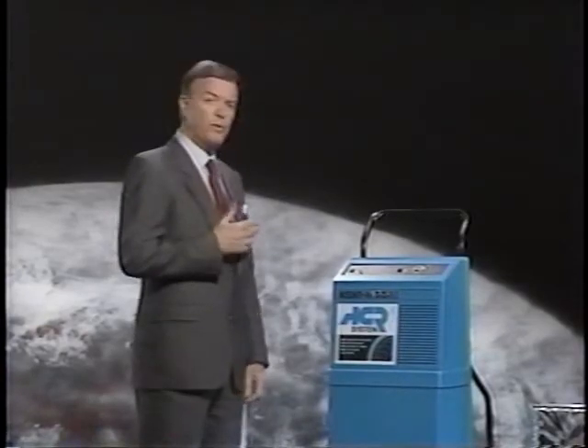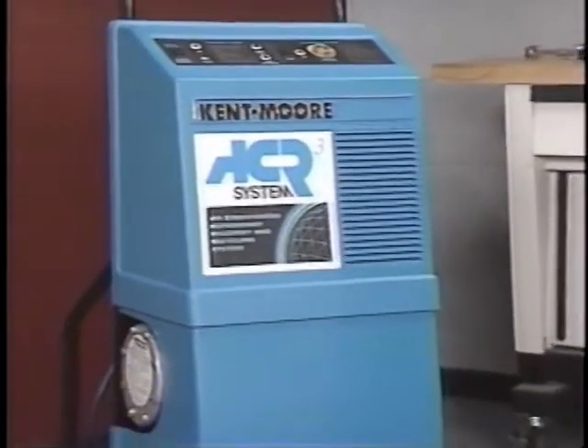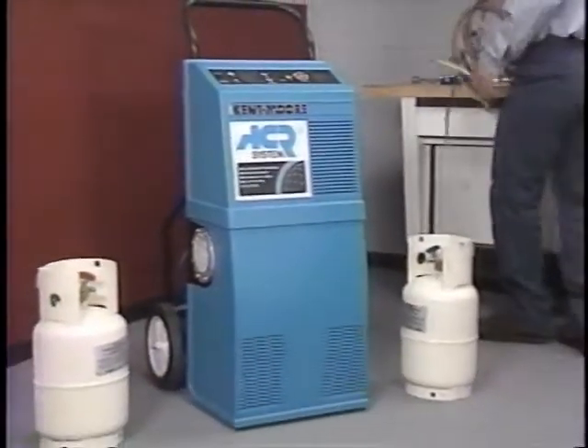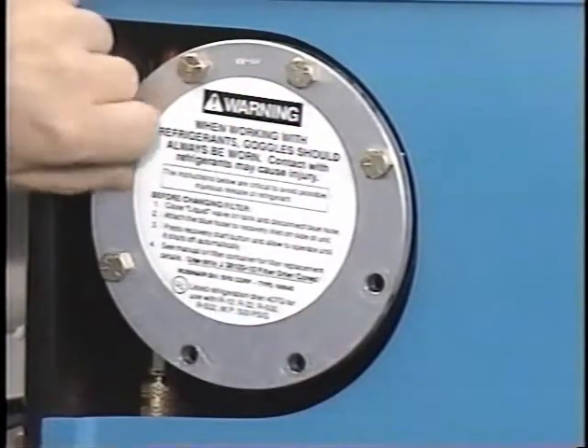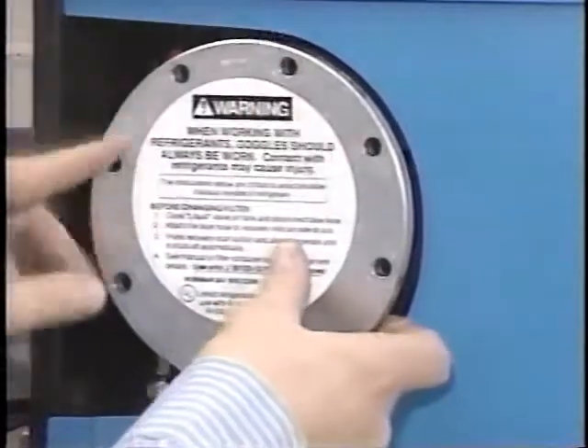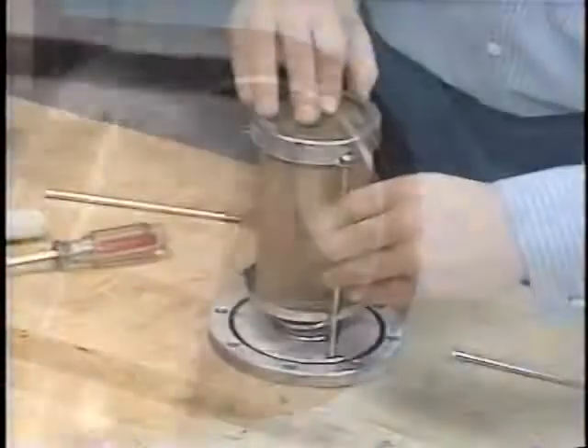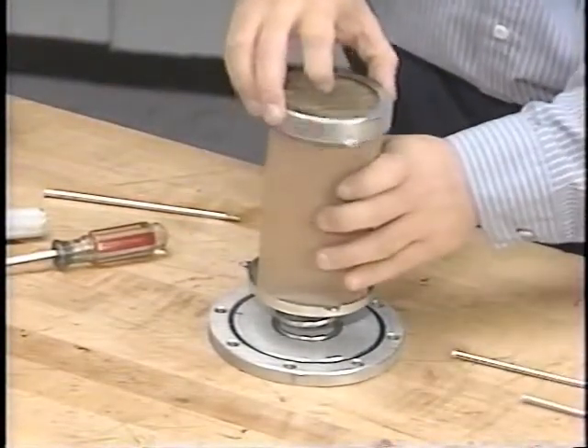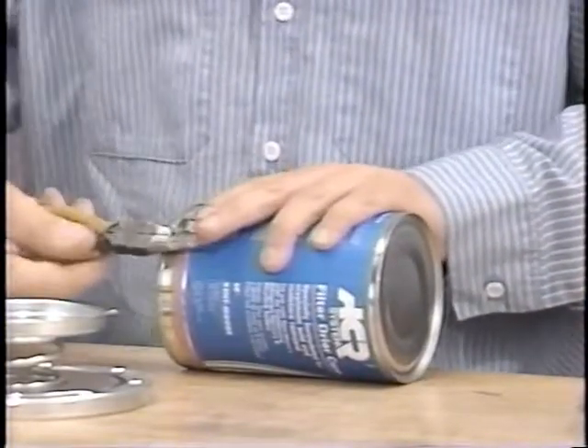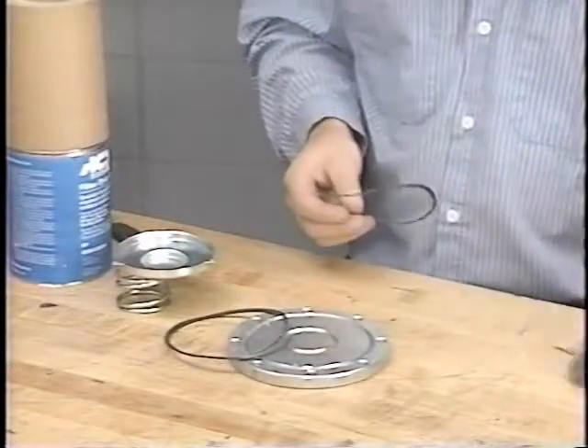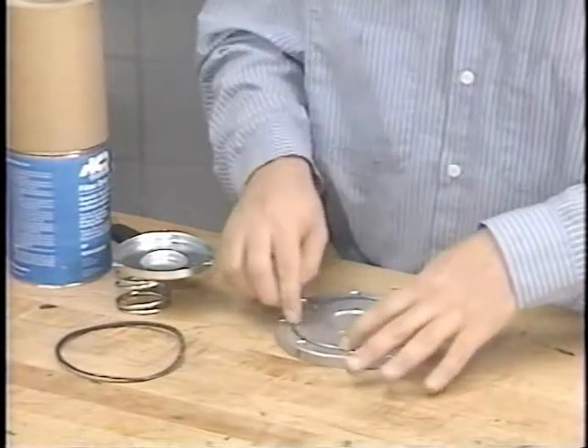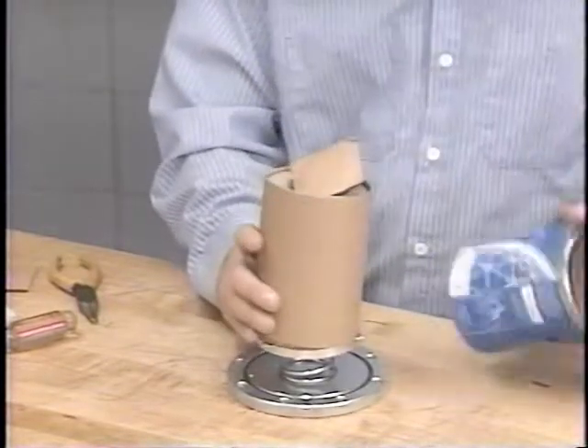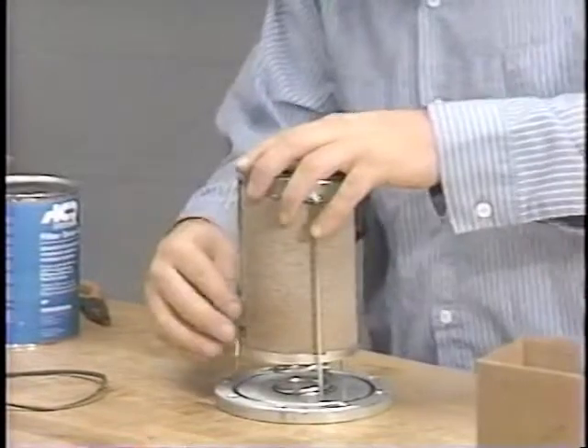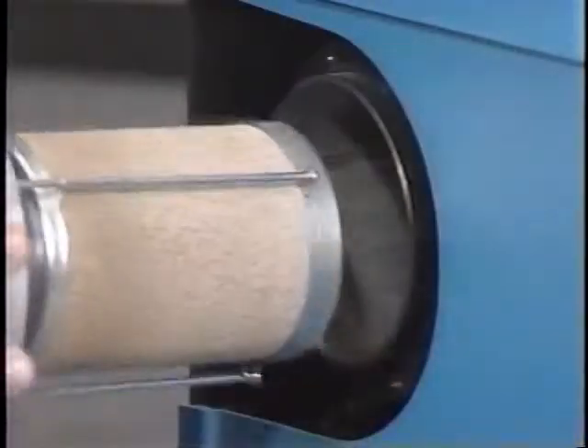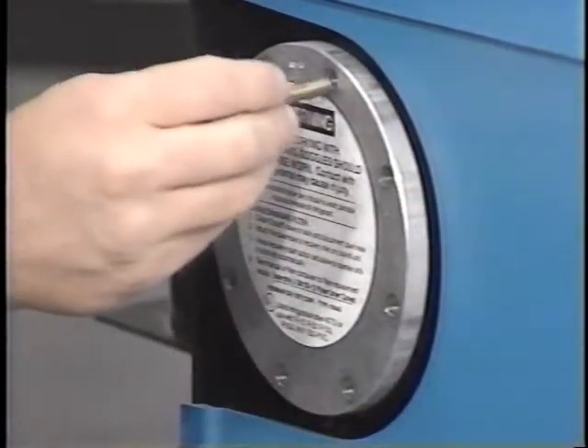To set up the ACR3 system for its first use, you'll have to install a filter and a tank. To install the filter, remove the 8 filter cap bolts and filter assembly. Discard the cardboard separator. Open the filter container and place a new gasket on the cap. Set the filter dryer core on the upper bracket. Place the lower bracket on the filter dryer core and install the tie rods. Insert the filter assembly into the filter shell. Install the 8 filter cap bolts. In a star pattern, torque the bolts.